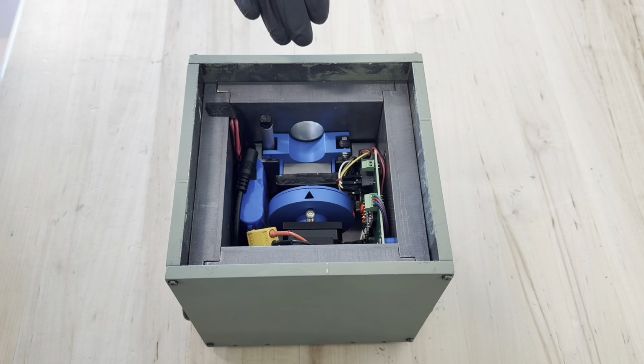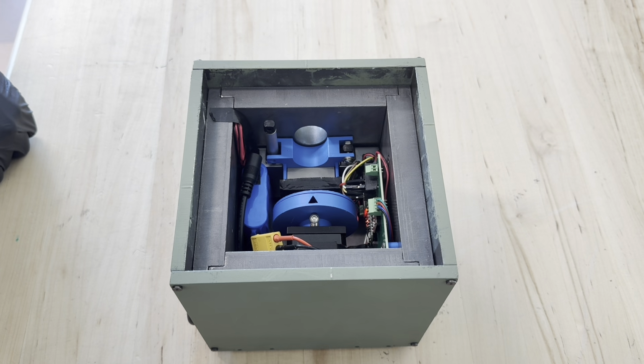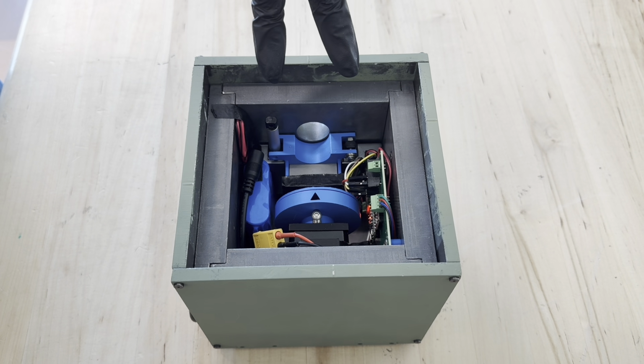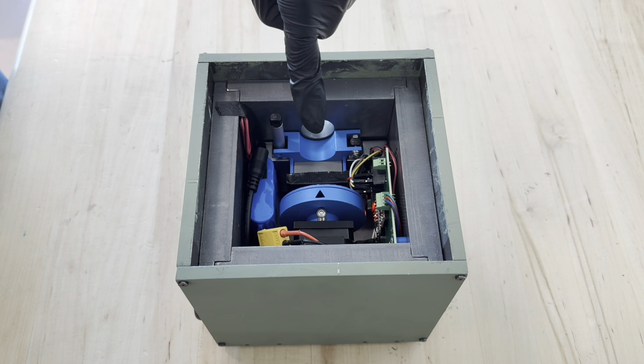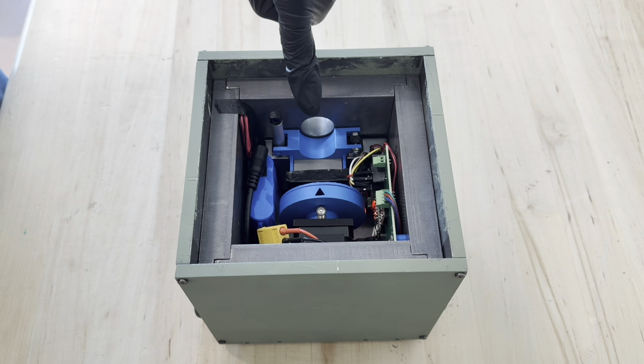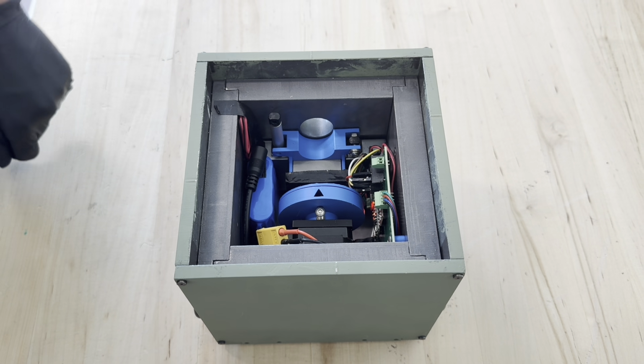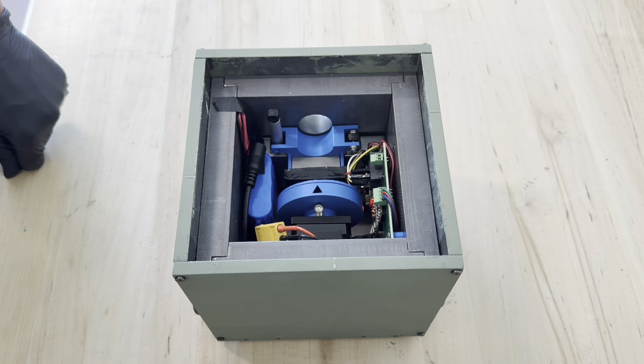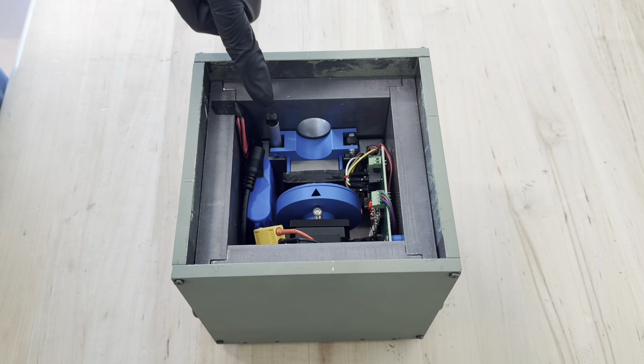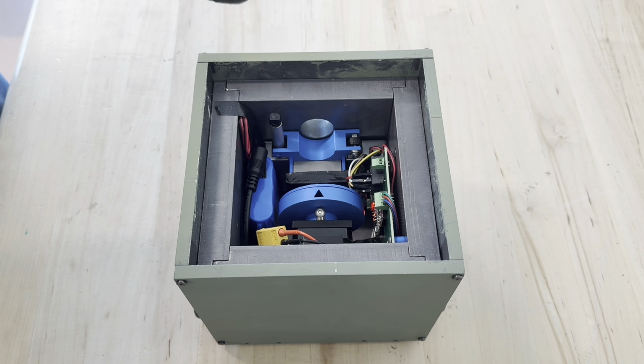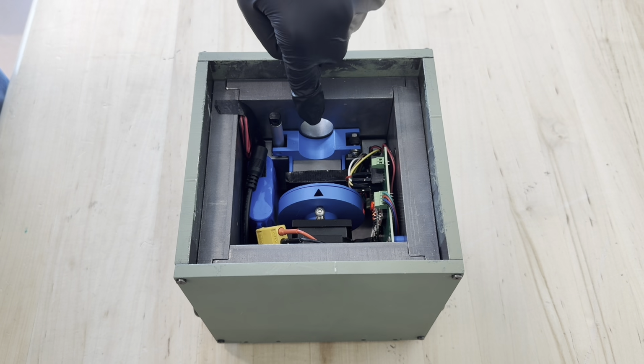This is our door assembly. It consists of 2 linear actuators, a tungsten block, and a 3D printed piece that connects the block to the actuators. The actuators can extend upwards, which also lifts the block up and lets it cover the chamber aperture.